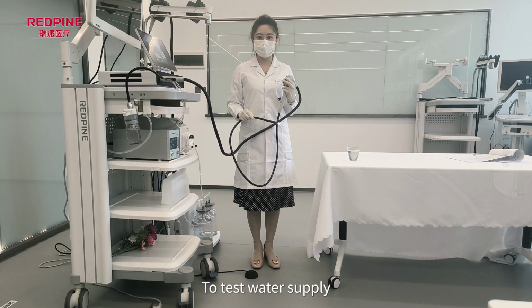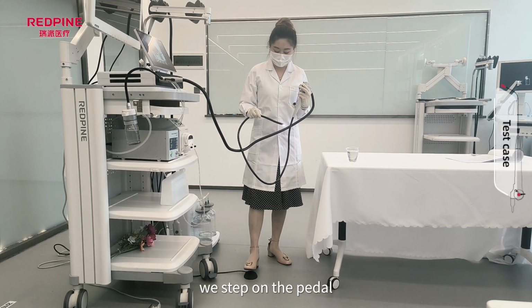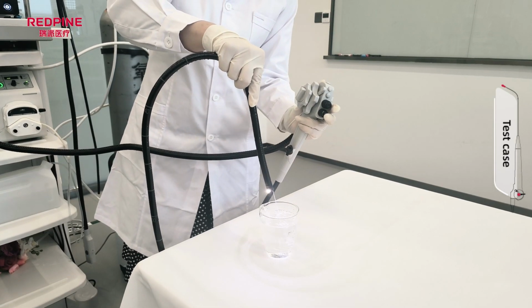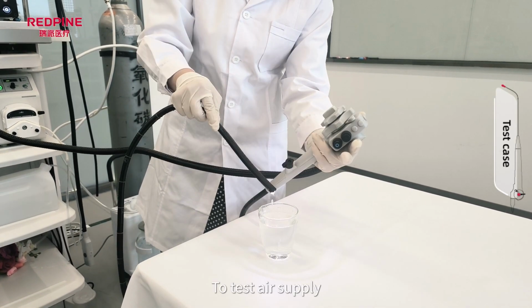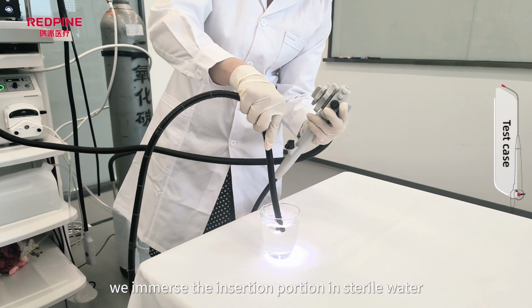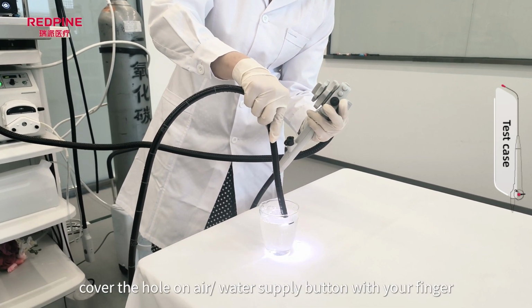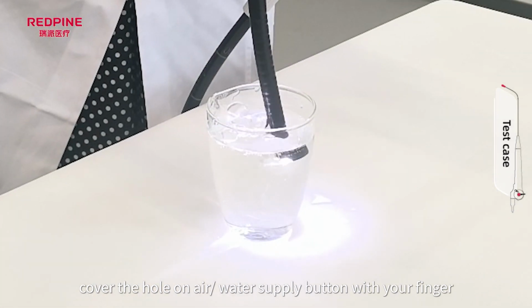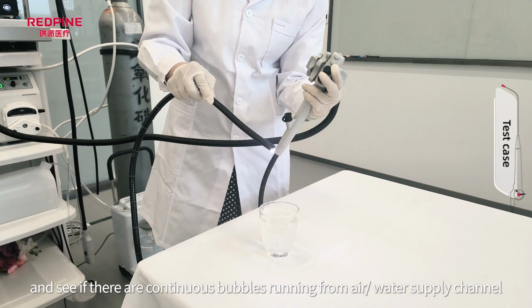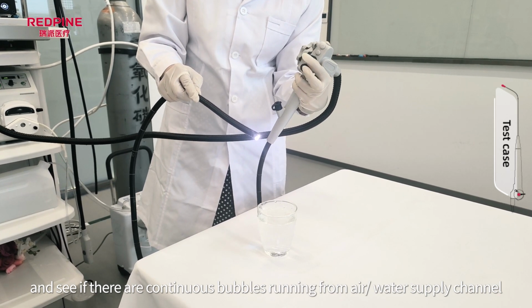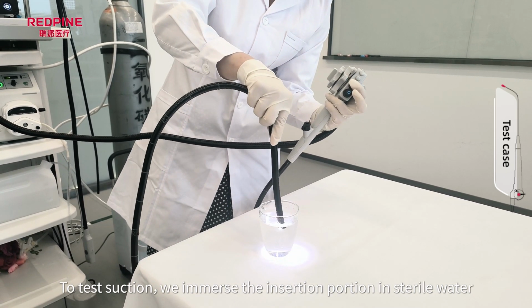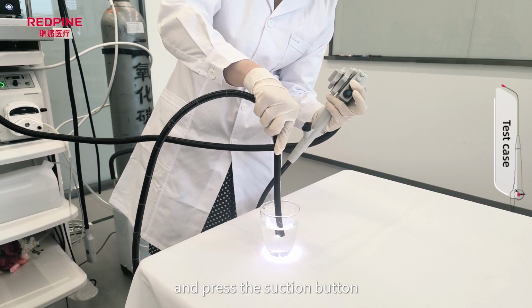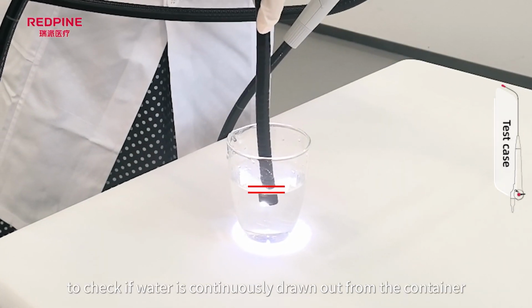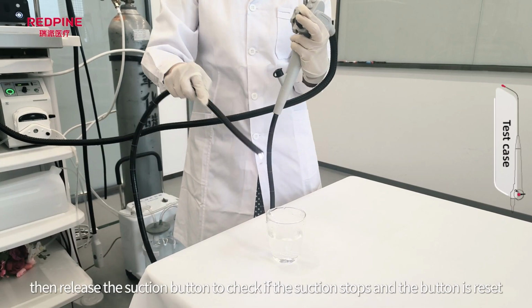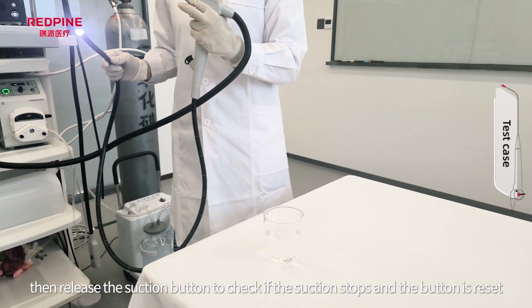The testing is started after the water pump runs normally. To test water supply, we step on the pedal and see if water is sprayed from the scope. To test air supply, we immerse the insertion portion in sterile water. Cover the hole on air or water supply button with your finger and see if there are continuous bubbles running from air or water supply channel. To test suction, we immerse the insertion portion in sterile water and press the suction button to check if water is continuously drawn out from the container. Then release the suction button to check if the suction stops and the button is reset.